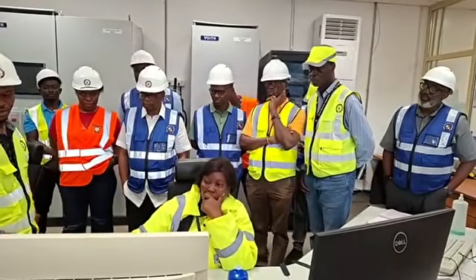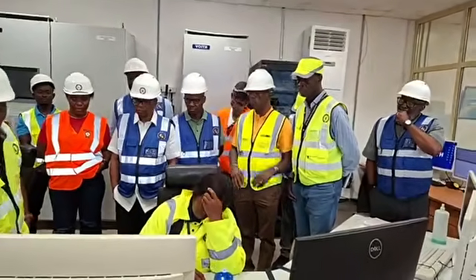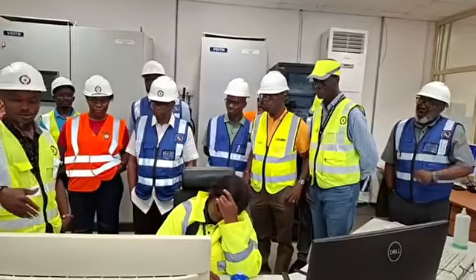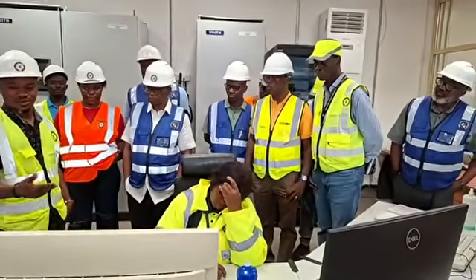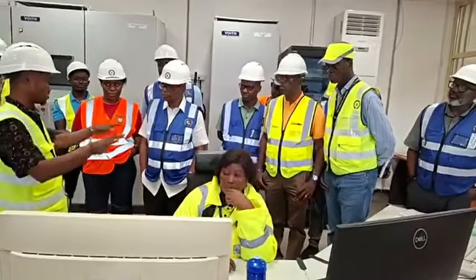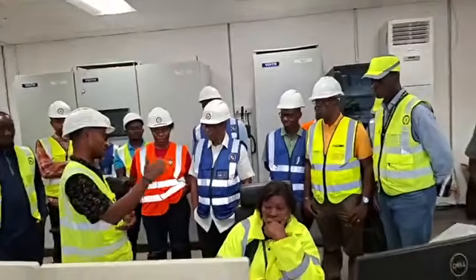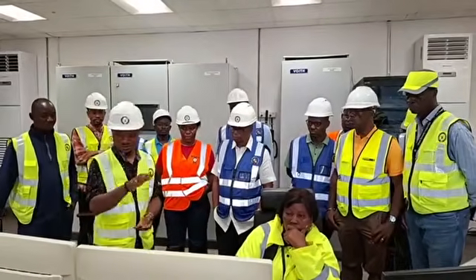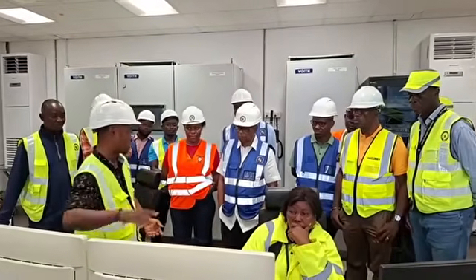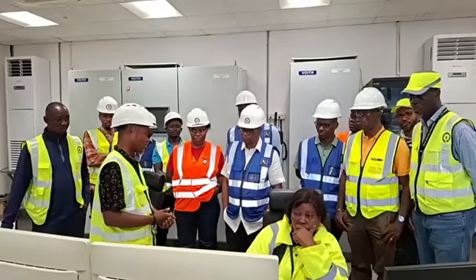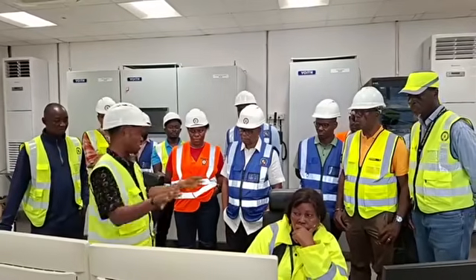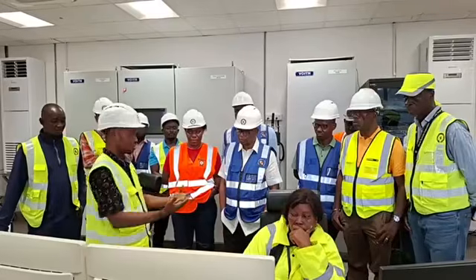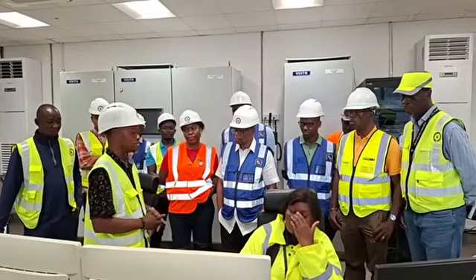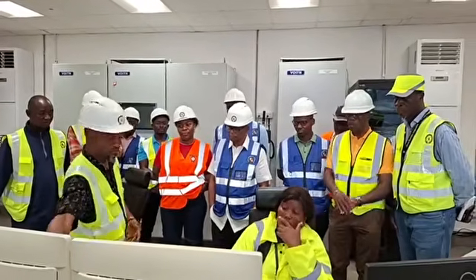So operator can decide to start at low load. Probably there was some maintenance work done, and the maintenance team want to do some inspection, and you don't want the unit synchronized at that station. So they give the first command at low load while the turbine is spinning. Then they do all of the unit inspection, and once the checks have been satisfied, then we can take the unit down to synchronize it.